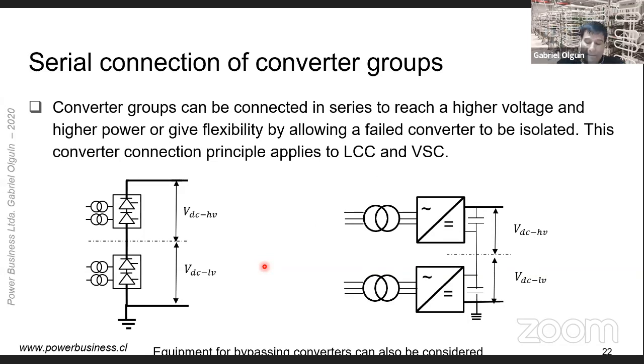Let's now review some possible configurations at each terminal of the link. At each terminal of the link, the converters can be configured to satisfy specific requirements, especially in terms of power and flexibility. Converter groups, for instance, can be connected in series to reach a higher transmission voltage for higher power, or for extra flexibility by allowing a failed converter group to be isolated. The converter connection principle applies to both LCC and VSC.